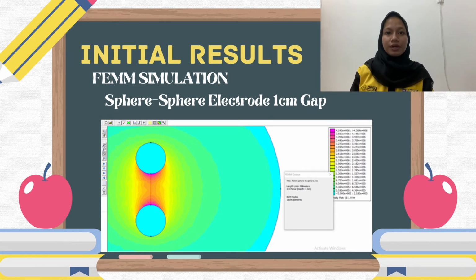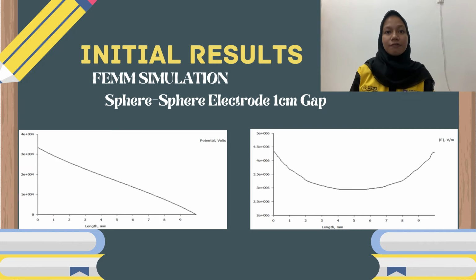By referring to the figure on the left, the voltage is decreasing from point A to B, and the bottom electrode does not have much voltage. From the figure on the right side, the minimum electric field occurs in the middle of the gap between the electrode spheres, which is around 2.9 megavolt per meter, and the maximum electric field occurs at points A and B, which is 4.4 megavolt per meter.